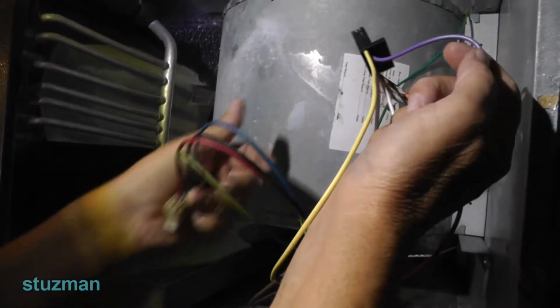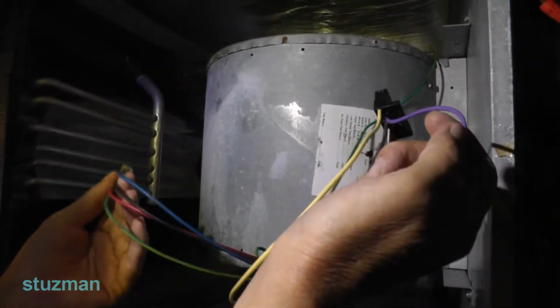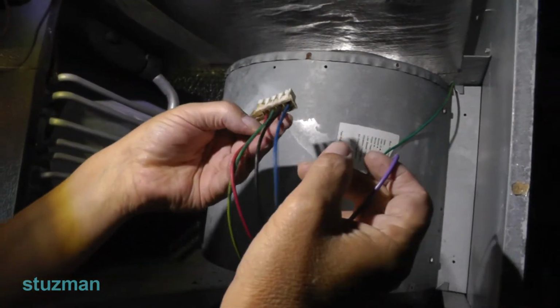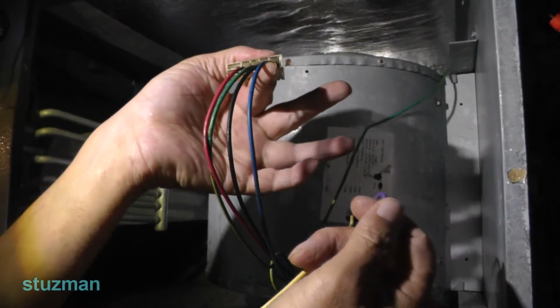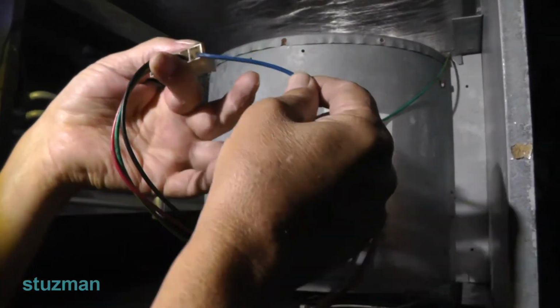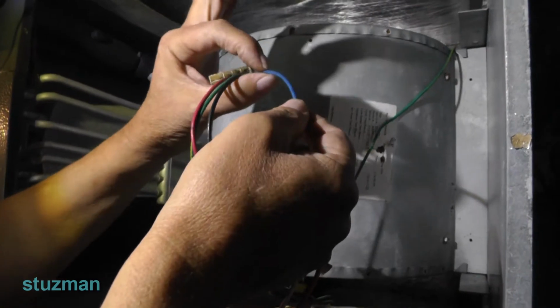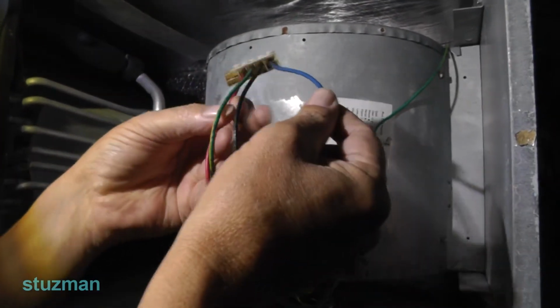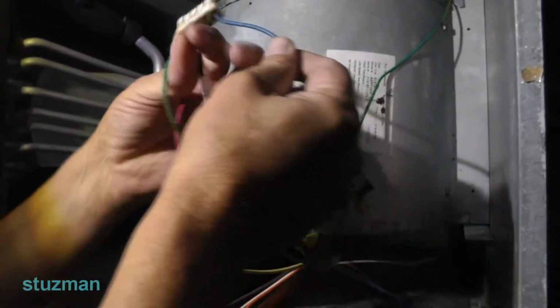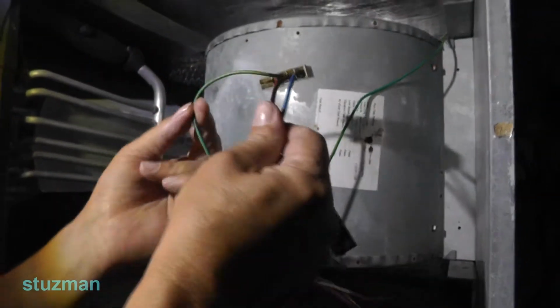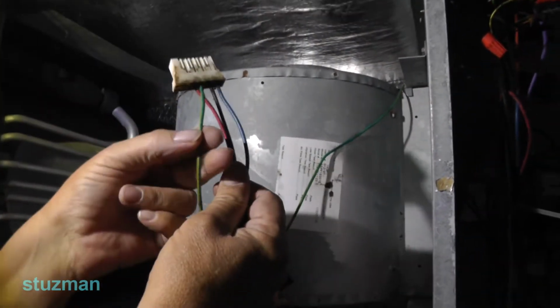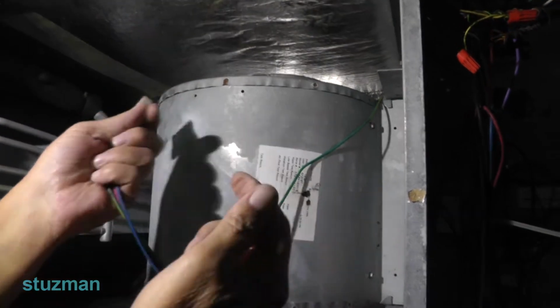Now, so I have my 24 volt AC coming in on this purple wire. Well, I need a common. They put it up here on the line power side, so that's this blue wire - this is going to be our C terminal. Now, the red and black wires are for the 240 volts AC coming in. Of course the green with the yellow stripe is the equipment ground.